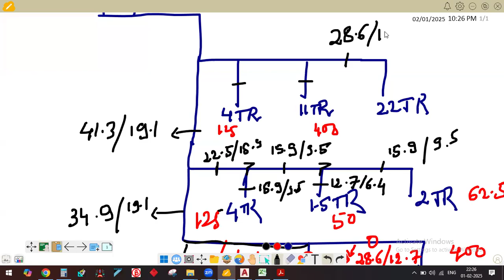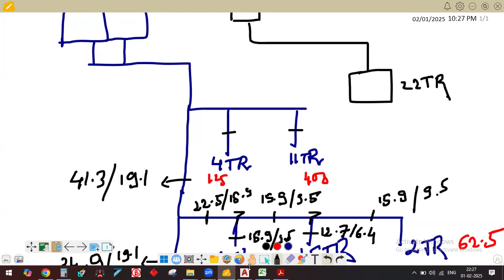Otherwise, what can I do? I will simply avoid this AHU here. I will take a separate VRF unit for the AHU. I hope you understood my point. I will not add it in this because I also have to check the capacity configuration here. So for this 22 TR, I am going to take a separate VRF outdoor unit. How much capacity is required here? Simply multiply by 1.25. So you require almost 30 HP. 27.5 means you require 30 HP here. So one AHU we are directly taking here.